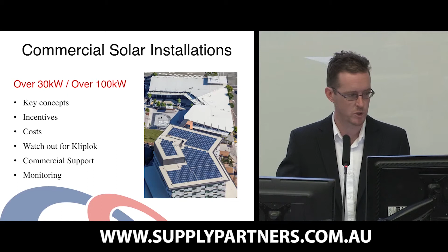Changing gears again, quick few comments about commercial installations. Export limitation, this is so common now in Queensland that I'm not going to go into export limitation particularly, except to say that 0 doesn't always mean 0. So you are allowed to export up to 1% of your inverter capacity or sometimes up to 2% of a dedicated transformer capacity for a site. I've got some graphs I'm going to show you in a sec, and what you'll see is that even though this particular site that I'll show you the graphs from is supposedly zero export, in actual fact we're allowed to export a little bit.